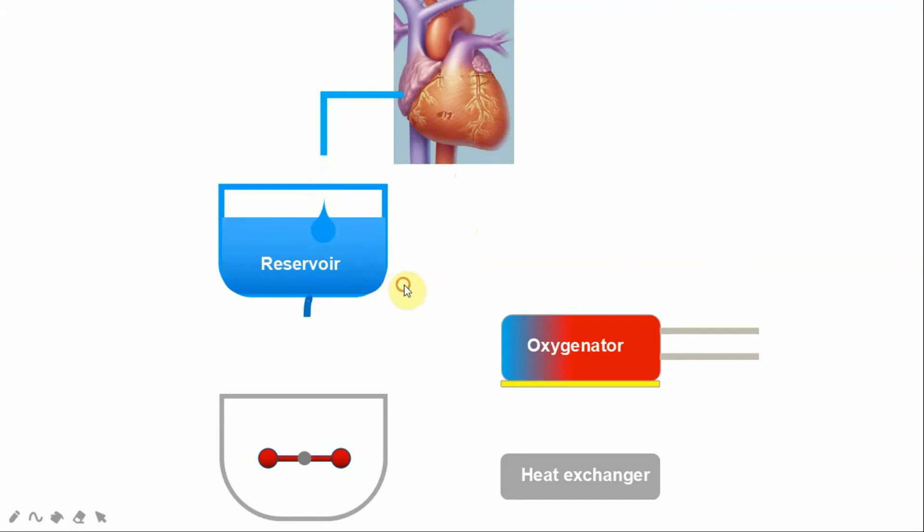From the reservoir, the blood is then taken to a pump system so that this blood can then go to the oxygenator. And this is unidirectional. The blood always goes from the reservoir to the oxygenator, not the other way around.